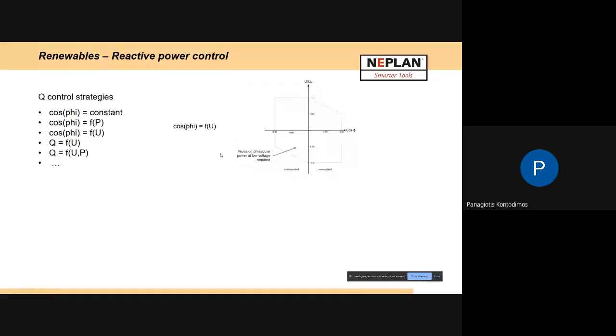So as you see here, I have a photovoltaic, and I can say my type is power factor as a function of voltage, and then I give my points, point by point. Here is the voltage: if the voltage is 100%, then the power factor is 0.9, not capacitive, inductive. And if my voltage goes to 90%, then my power factor is 0.9 capacitive. So it tries to maintain the voltage in a range, let's say.